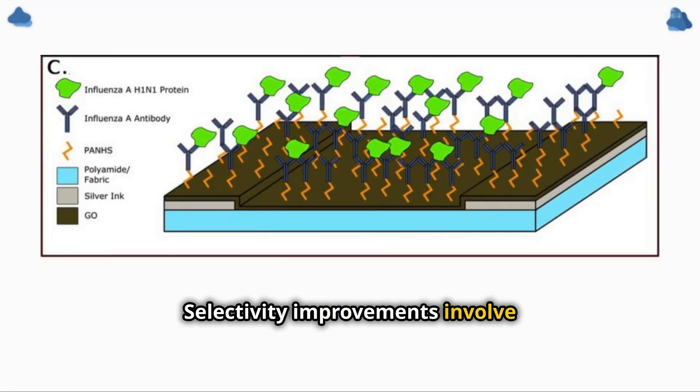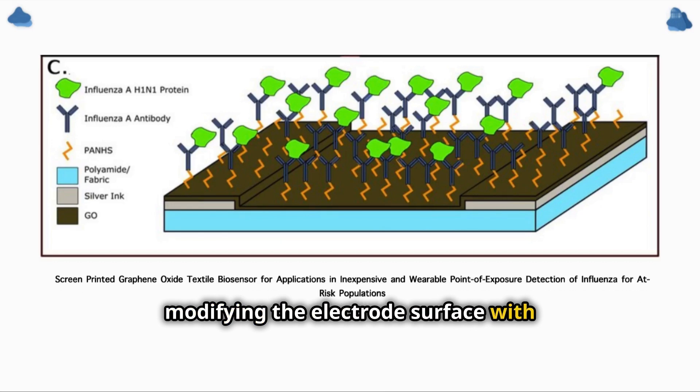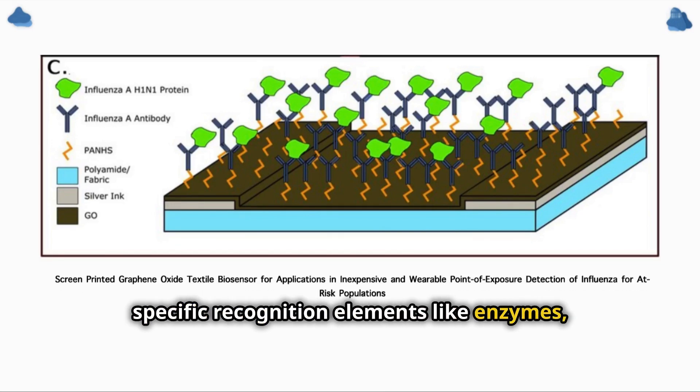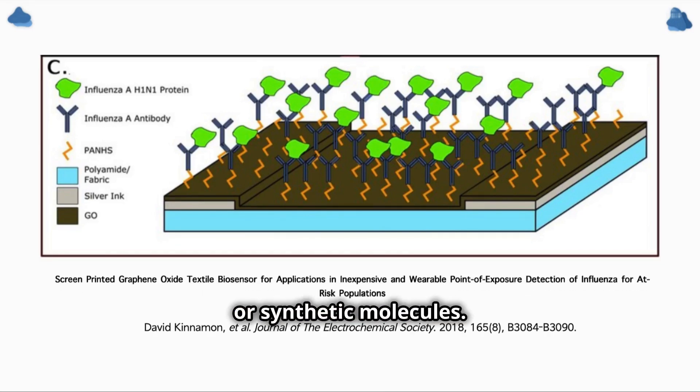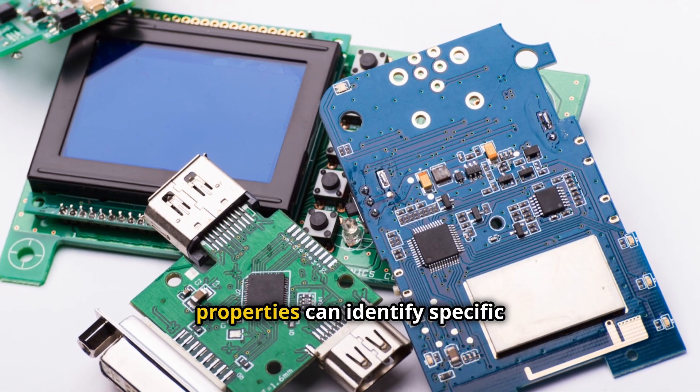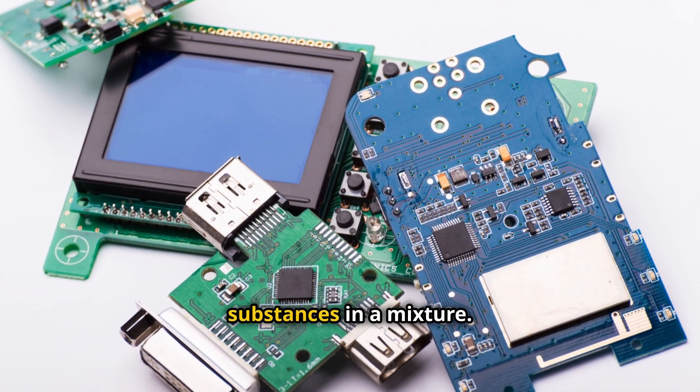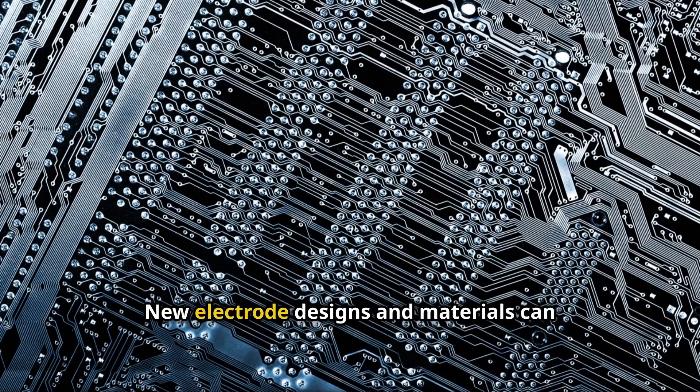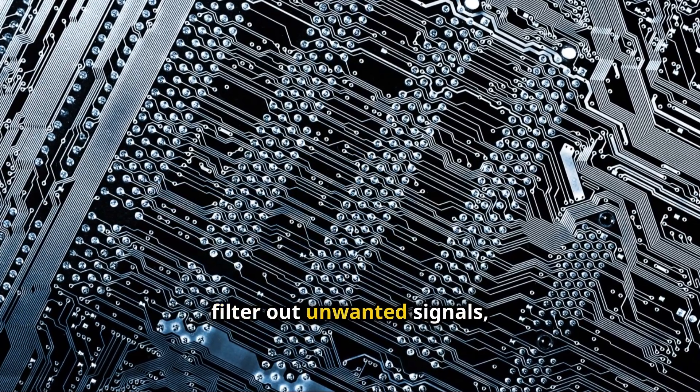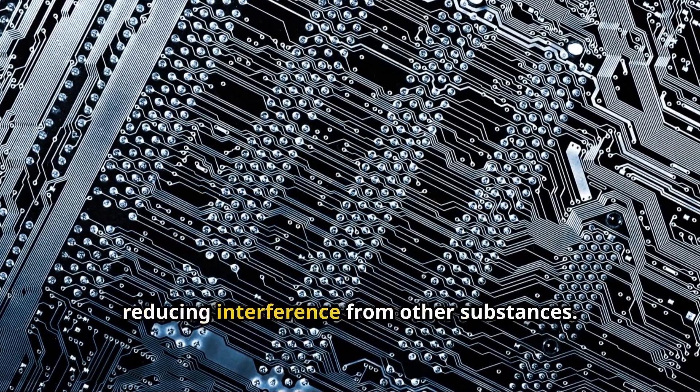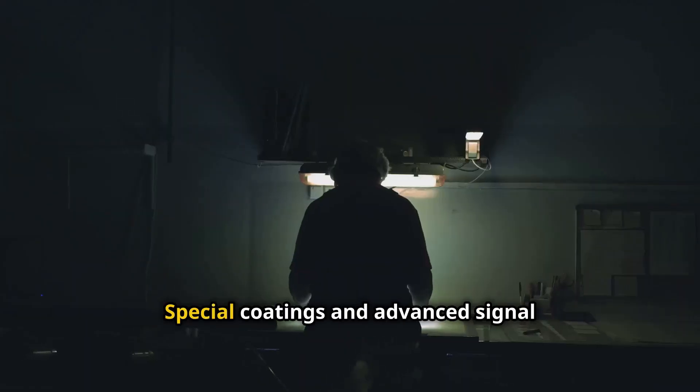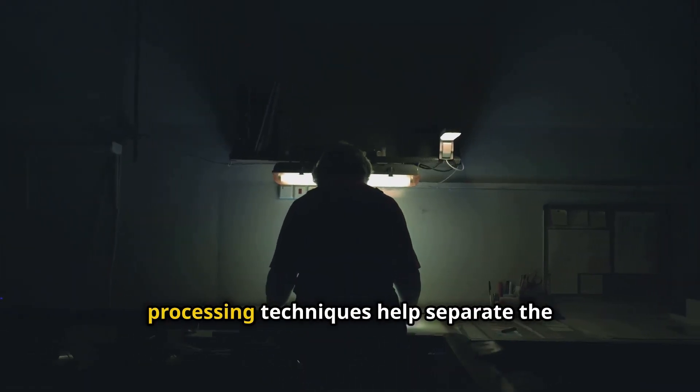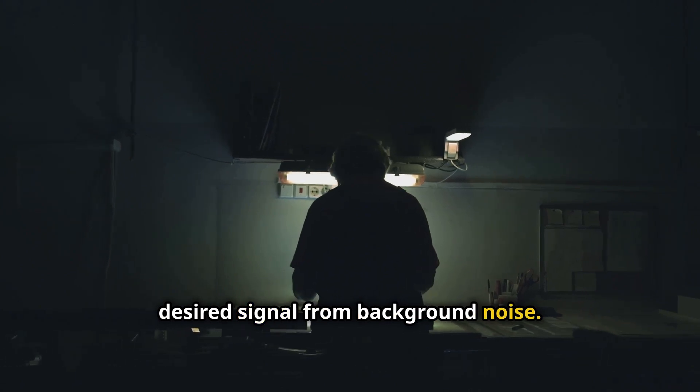Selectivity improvements involve modifying the electrode surface with specific recognition elements like enzymes, antibodies or synthetic molecules. Arrays of electrodes with different properties can identify specific substances in a mixture. New electrode designs and materials can filter out unwanted signals, reducing interference from other substances. Special coatings and advanced signal processing techniques help separate the desired signal from background noise.